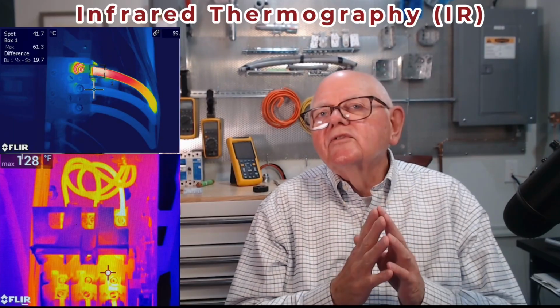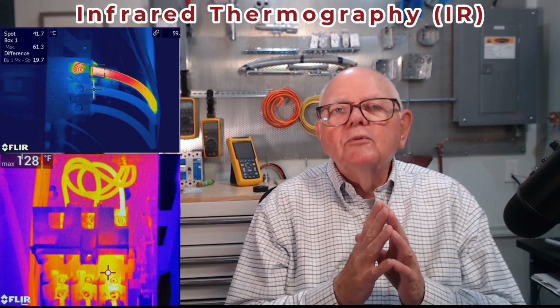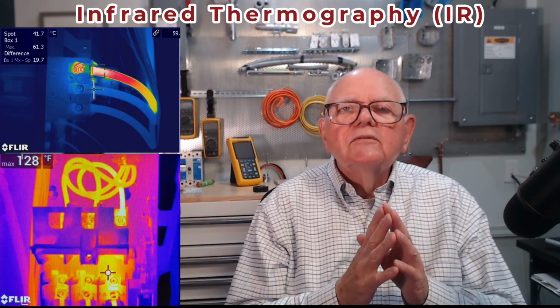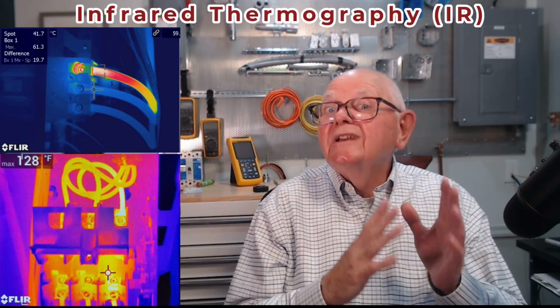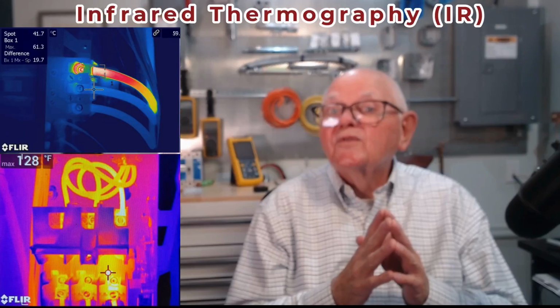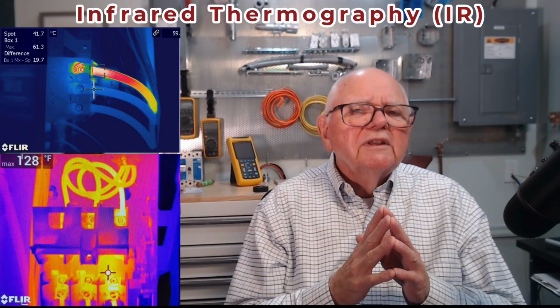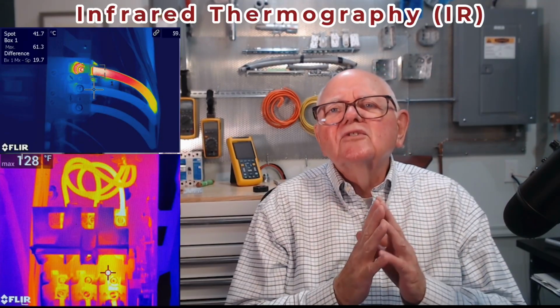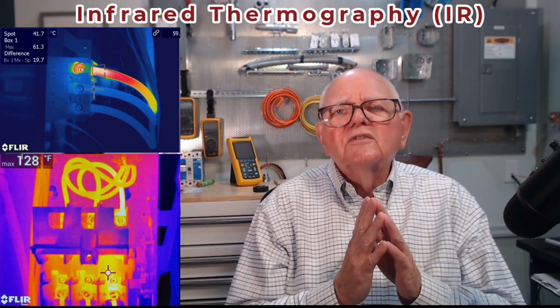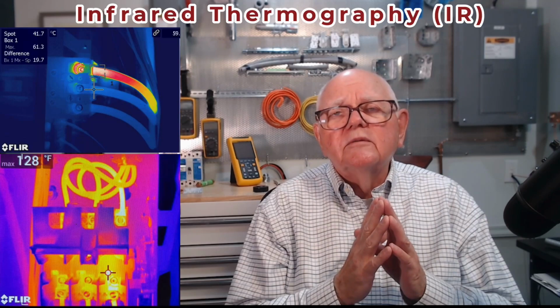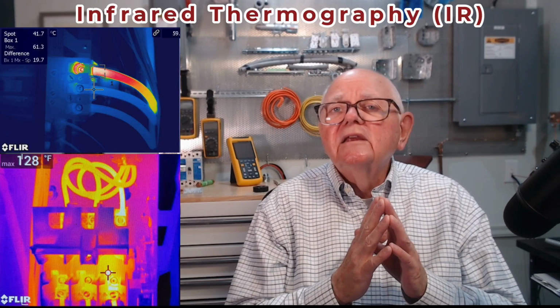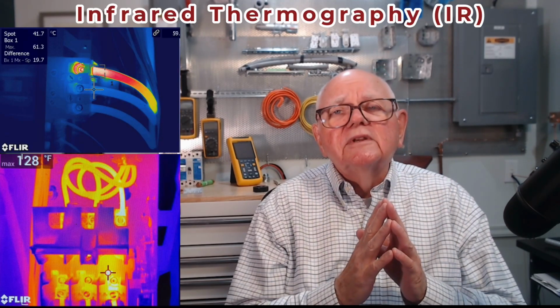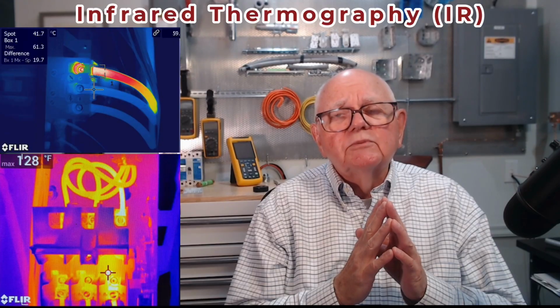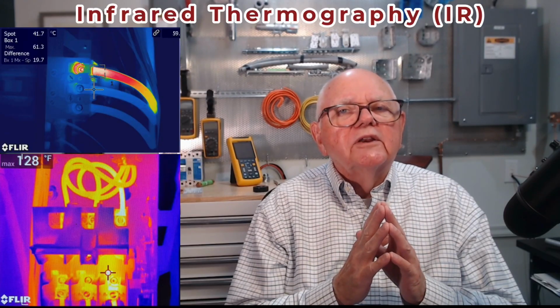So generally 1 to 3 degrees C between 2 terminal points, we're not too concerned about, or 3 to 15 degrees. By the time we're getting up towards 15, we're getting concerned with it. At 16 degrees C and greater between 2 test points that we're looking at on an image, it says go ahead and probably shut your equipment down and repair that as quickly as possible. Then you have something that's about ready to fail.